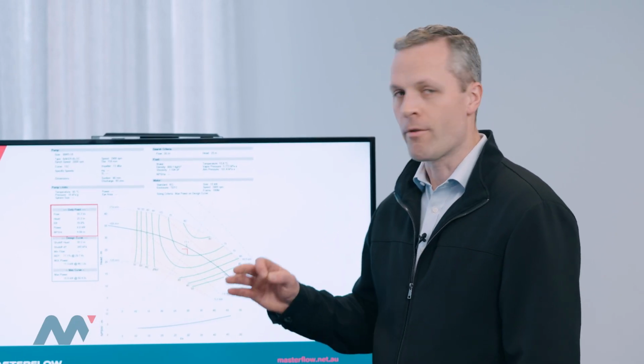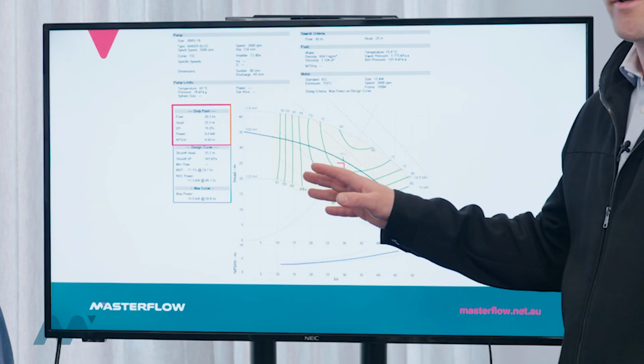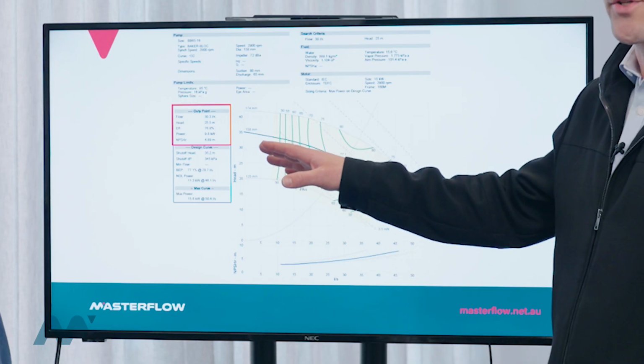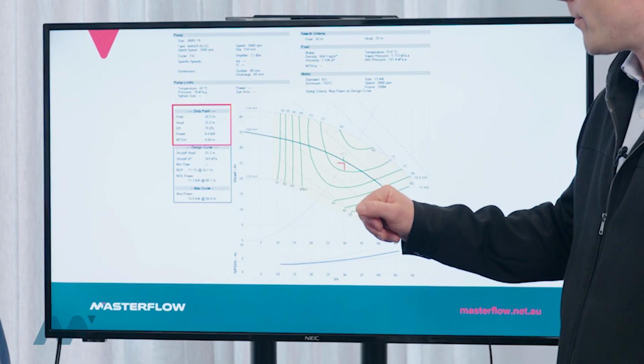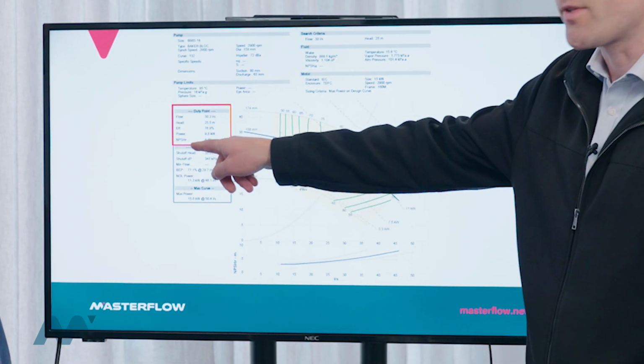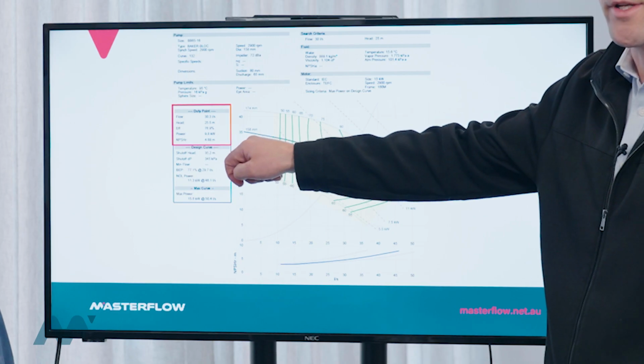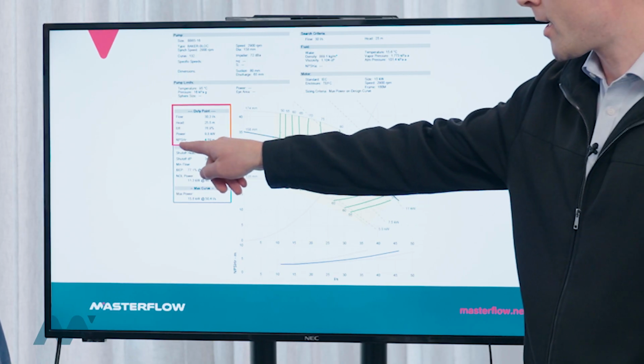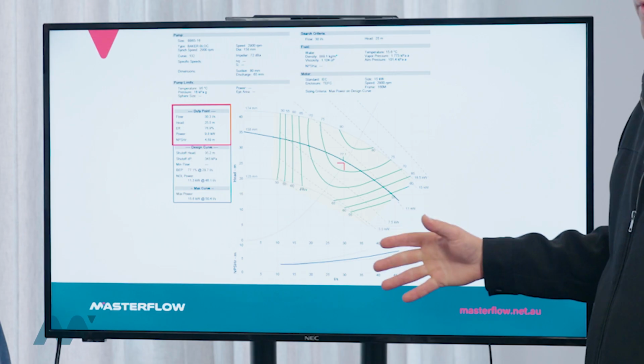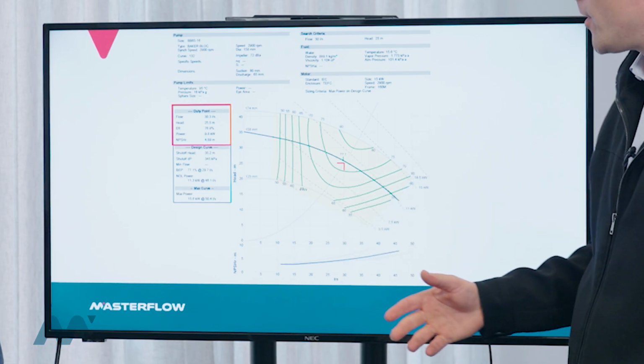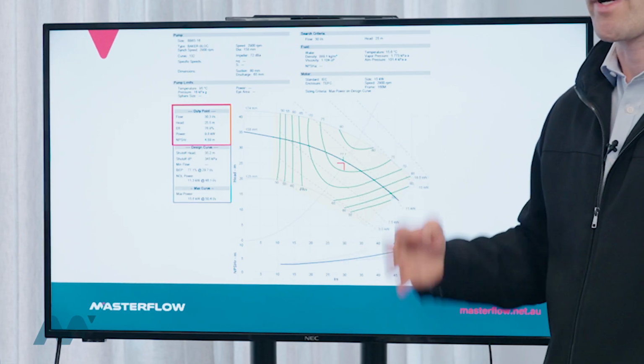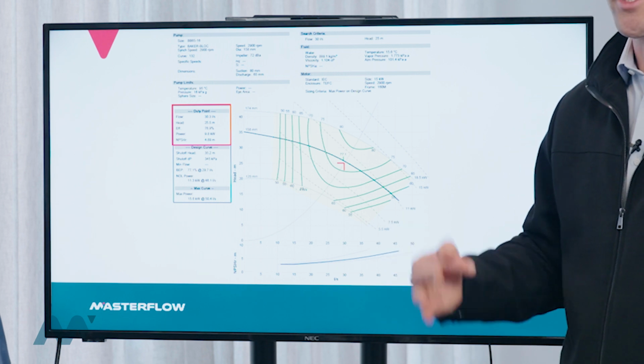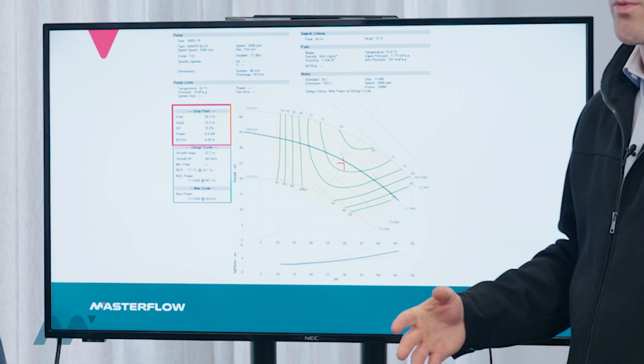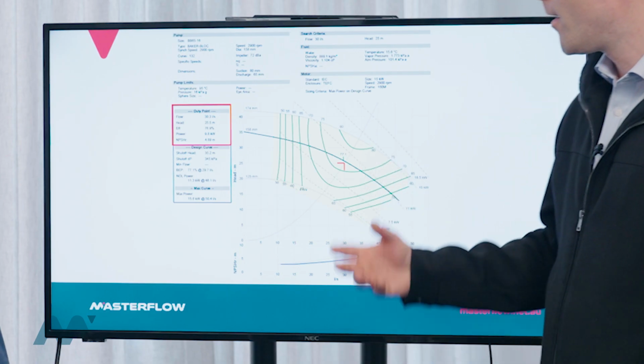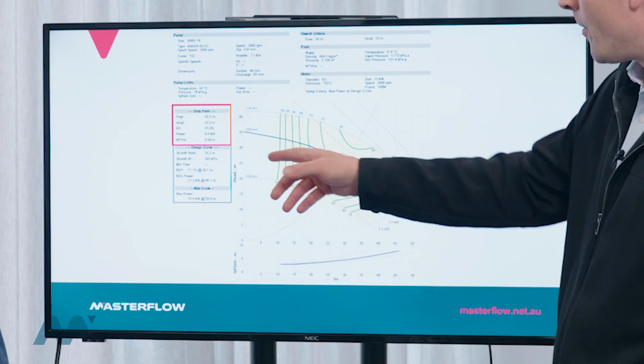So in conclusion, it's very important that you're sizing your pipe work for the right velocity and that you're selecting a pump that has as low a net positive suction head required as possible. In this situation, the net positive suction head required was 4.89 metres. It's very important to always check the NPSH when you're dealing with condenser water pumps on an open cooling tower. I'm talking primary condenser water pumps, not so much secondary condenser water pumps, because secondary condenser water pumps are generally on a closed loop. Open or primary condenser water pumps are on an open loop.